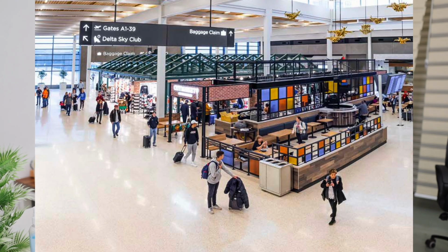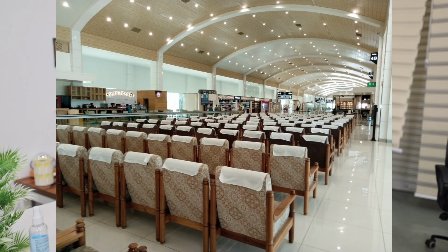For example, you are making HVAC for a big airport, and the rush is too much, and so many people are standing. Of course, there is more heat. So in that situation, there are occupancy sensors. It will sense the people, and of course, it will sense the heat. And depending on that, the BMS system will give the command to the chilled water system and the chillers. So it will increase the efficiency. If it is not required, it will decrease the efficiency so that they can save the electricity, the power, like that.